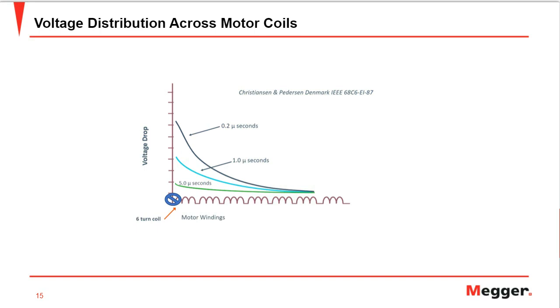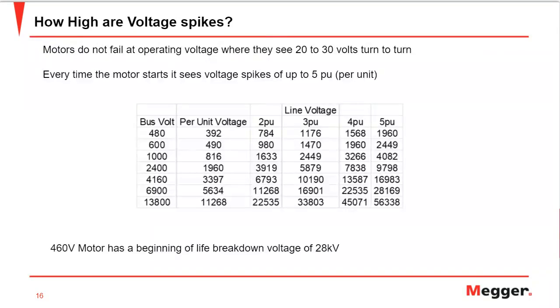And we have previously discussed that more voltage stress appears at the first turns. That's why motors fail at early turns most of the time. There are various voltage spikes generated because of various reasons. We'll see how high these voltage spikes can go at the initial start of the motor. As you can see, for a 480 volt motor, it can go up to 5 times the per unit value, which is around 1960.